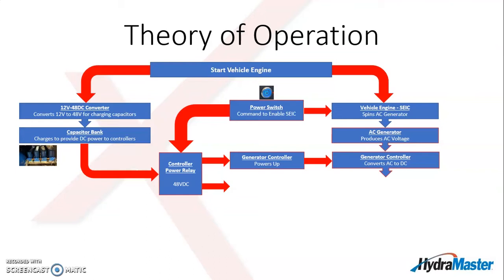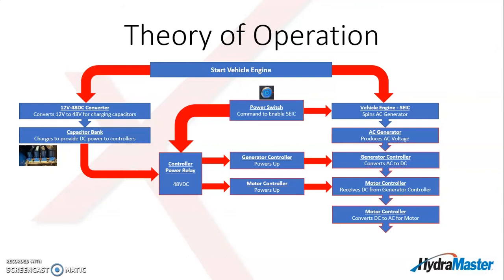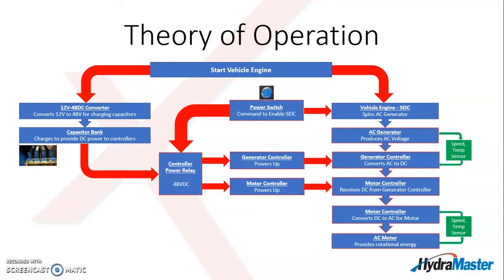It's producing AC voltage. The AC voltage is fed into the generator controller. The controller converts that AC voltage coming from the generator into DC voltage. That's provided to the motor controller. The motor controller in turn transforms that DC voltage back into AC voltage to spin the motor and the blower and the pump. And that's what turns the system. Both the generator and the motor themselves are controlled by the controllers, but they also have a speed sensor and a temperature sensor inside each motor that's providing feedback to the controllers. That's kind of the overview of how the whole system starts up and generates power.